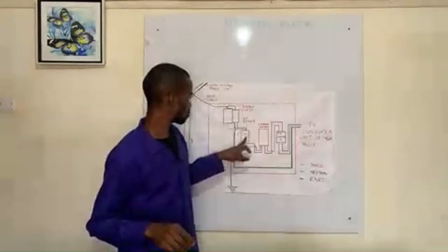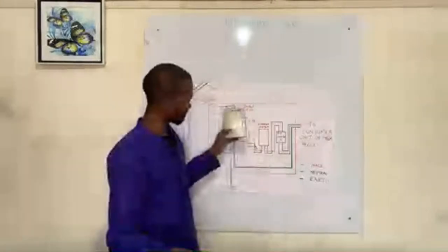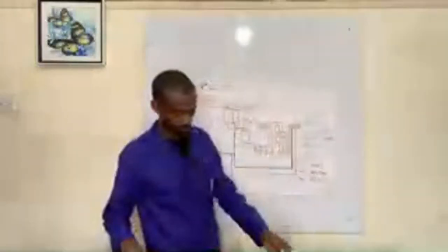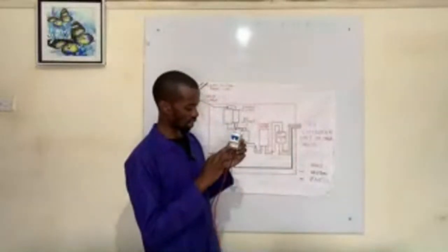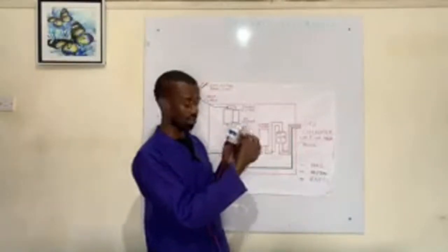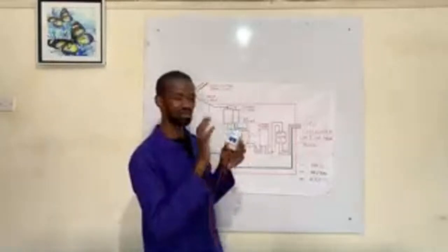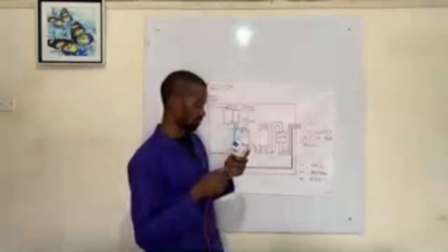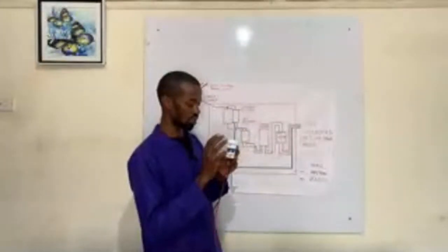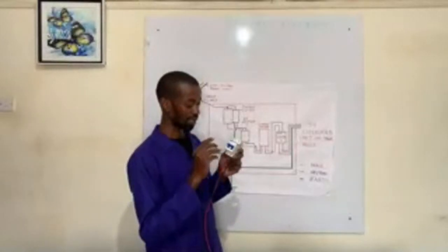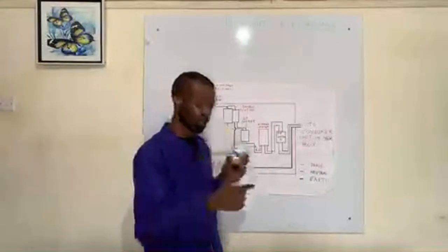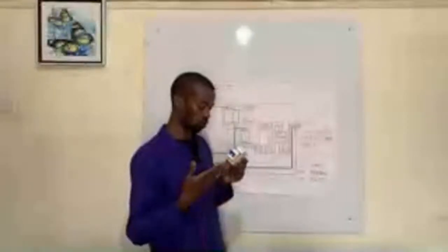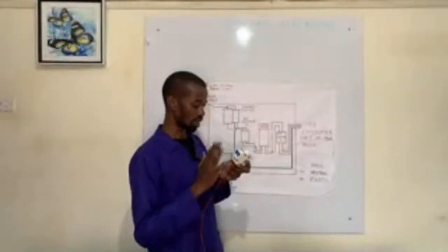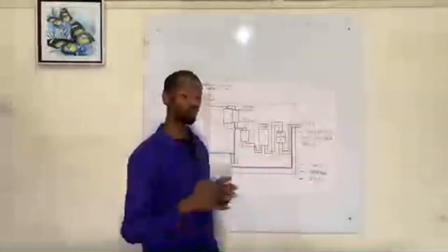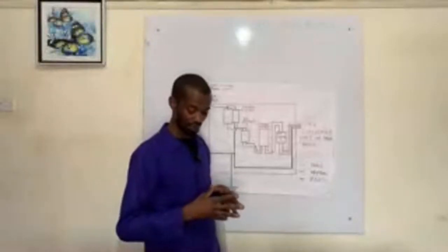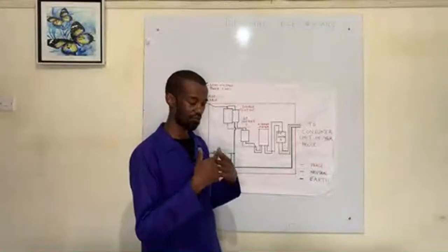And when it comes to the double pole switch, the first one that is actually energizing this meter from the cutout, again, like we've indicated earlier, it's important to have those wires, the ones coming in and out of the switch, very, very tight. Why? Because this double pole switch is interrupting the path of electricity, and when it is interrupting, we need to make sure that path is very easy for electricity to flow through. So whenever we create that interruption through this switch or device, we must ensure it is very tight and smooth, or safer and easier for electricity to flow.